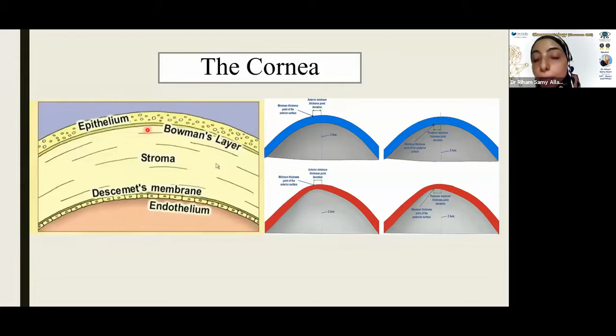We all know that the average normal central corneal thickness is around 520 to 540 microns. The Goldmann applanation tonometry is well calibrated for the 520 range of corneal thickness. However, this is not the normal range of our population. So studies have estimated that for every 10 microns difference from the normal, we should adjust the intraocular pressure. The thin cornea gives an underestimation of the intraocular pressure, so we have to add to our measurements.